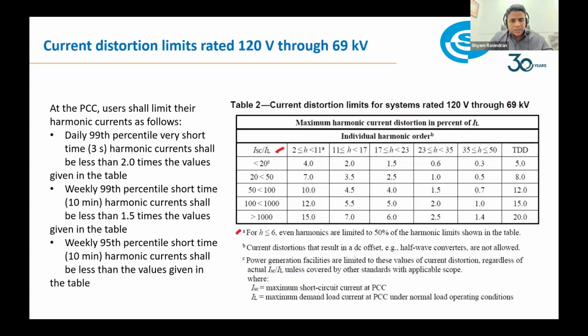Let me quickly show, from the old standard, what is the difference now? The old standard clearly talked about THD. It was the only one defined. THD on my current shall be less than 8%. THD on my voltage shall be at 5%. Even though THD V has significantly no influence by the customer, at the PCC the THD V shall also be maintained, and the individual harmonic components shall also be maintained.